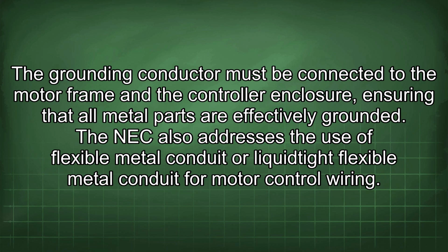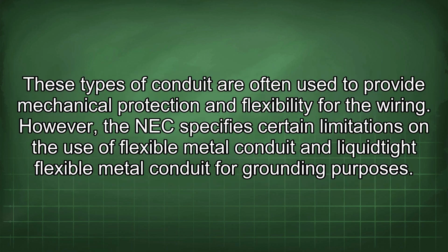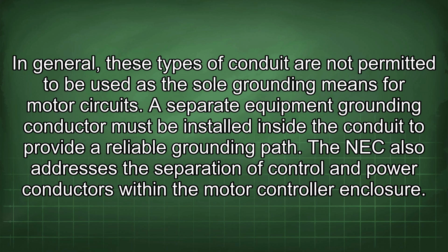effectively grounded. The NEC also addresses the use of flexible metal conduit or liquidtight flexible metal conduit for motor control wiring. These types of conduit are often used to provide mechanical protection and flexibility for the wiring. However, the NEC specifies certain limitations on the use of flexible metal conduit and liquidtight flexible metal conduit for grounding purposes. In general, these types of conduit are not permitted to be used as the sole grounding means for motor circuits. A separate equipment grounding conductor must be installed inside the conduit to provide a reliable grounding path.